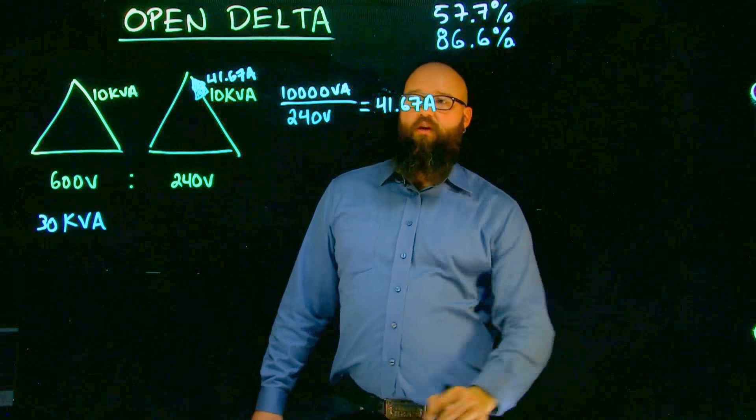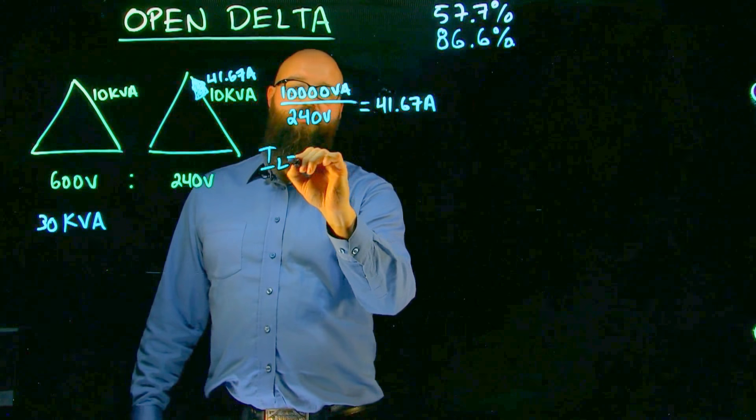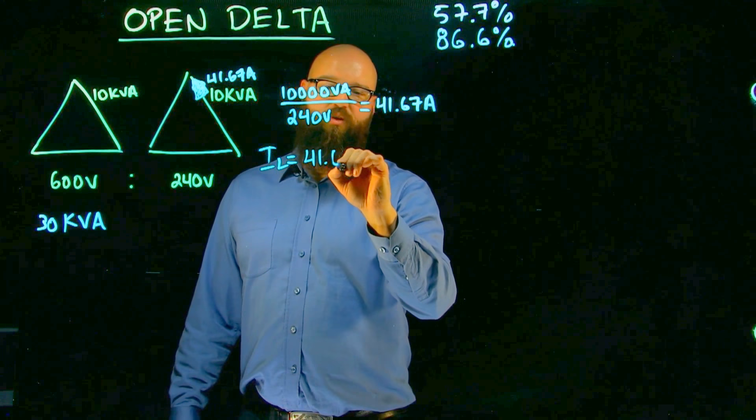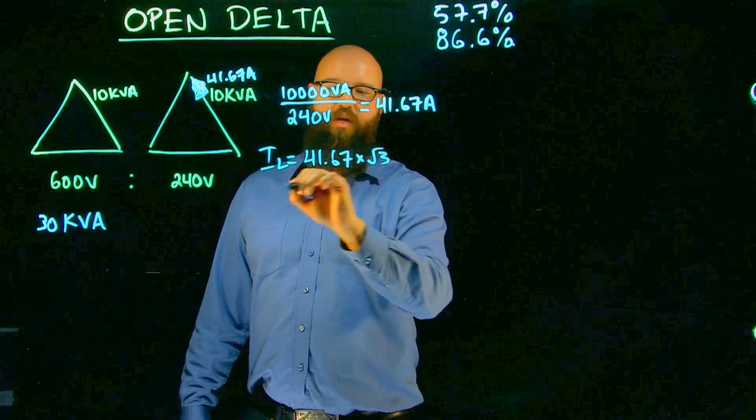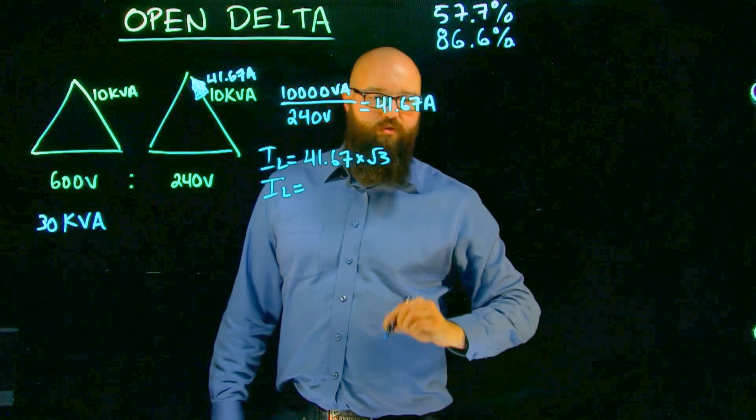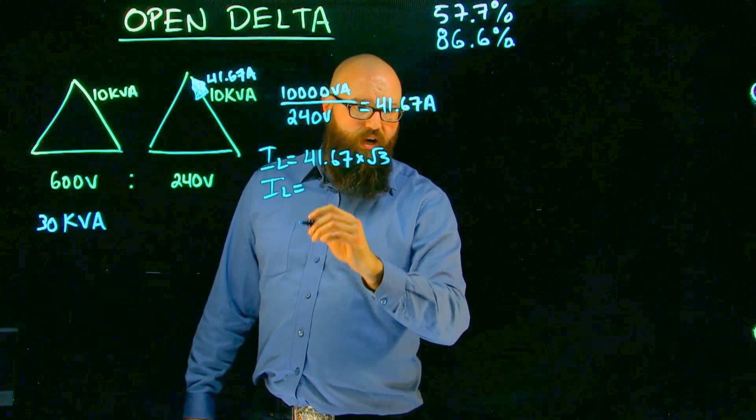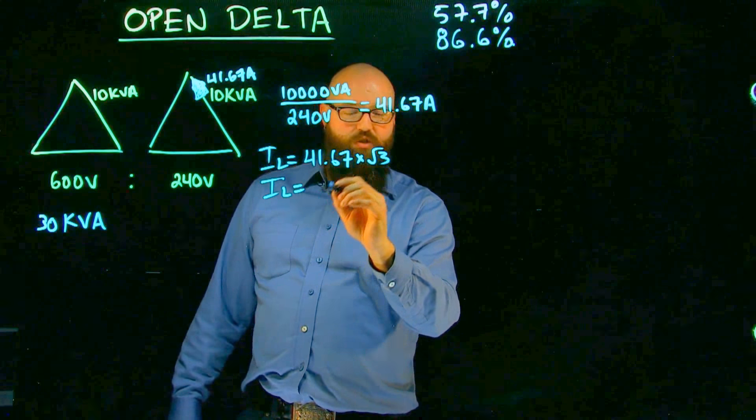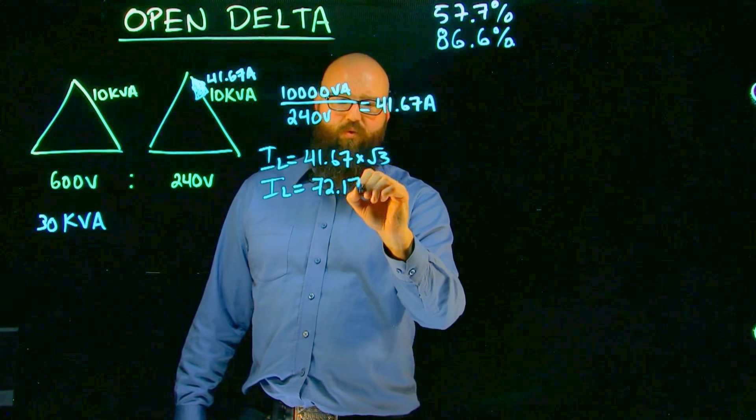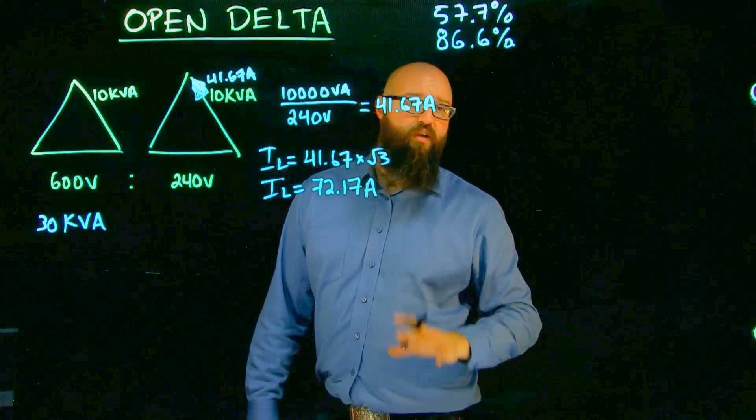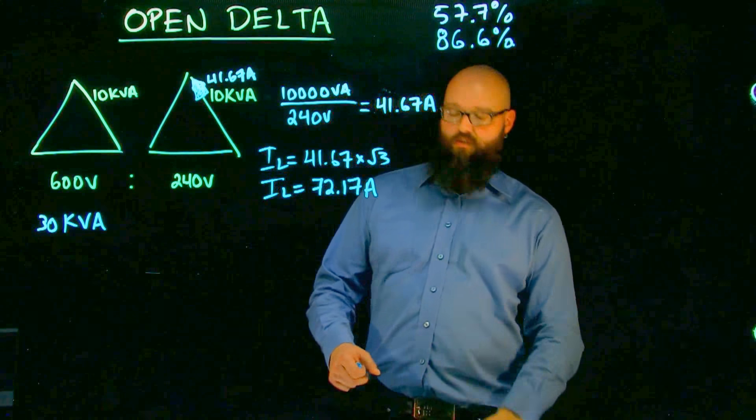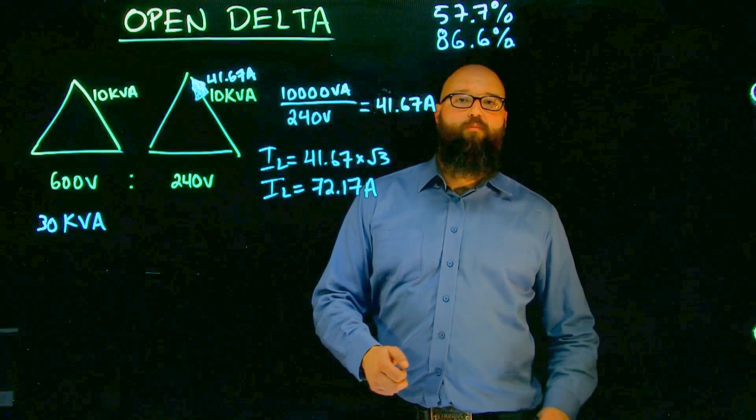Delta connection, it also means that my I line is equal to 41.67 times root 3. I line equals, we should see, around 72.17 amps. Okay, that's under normal circumstances with all three of our transformers connected in.